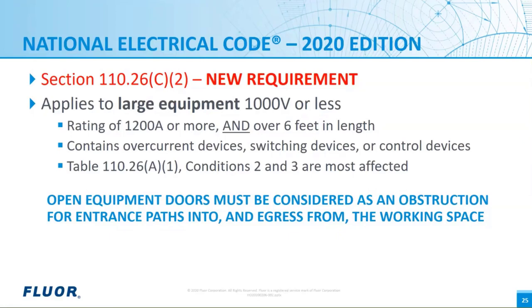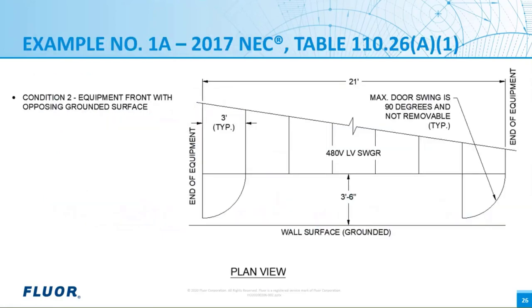In supervised industrial facilities, there are many places throughout the NEC where requirements are not the same as for residential or commercial installations. And we'll talk more about that. In this example, we show what was legal in the 2017 NEC. This is a plan view of a piece of large electrical equipment. This is a condition number two, where you have exposed live parts on one side and a grounded surface opposing the front of the equipment.